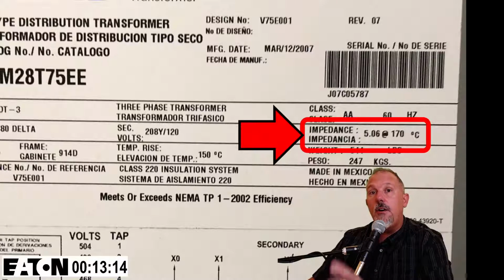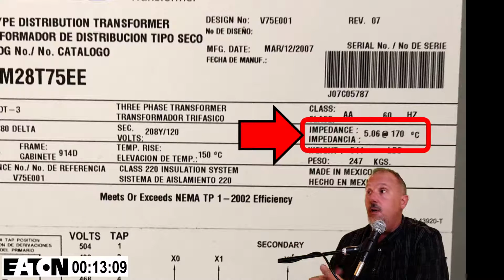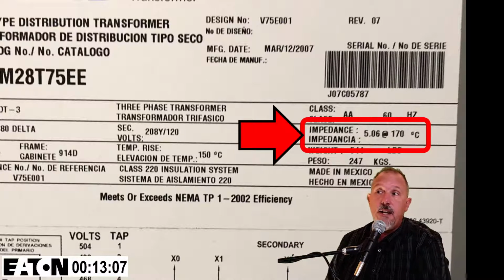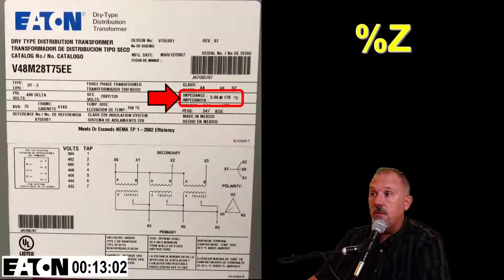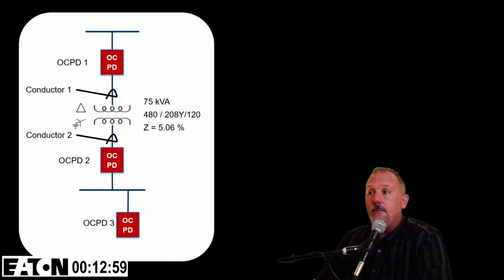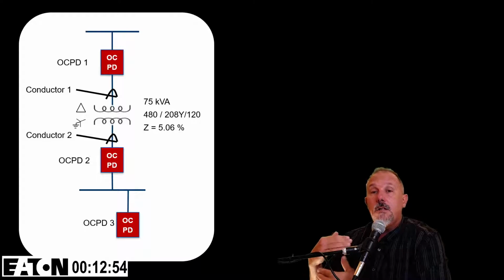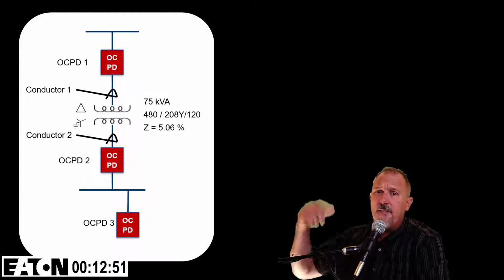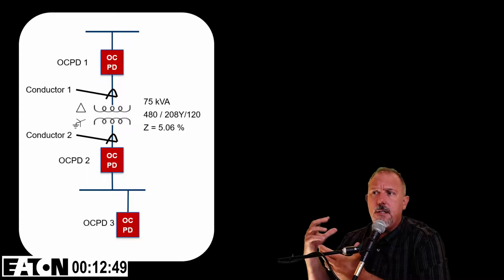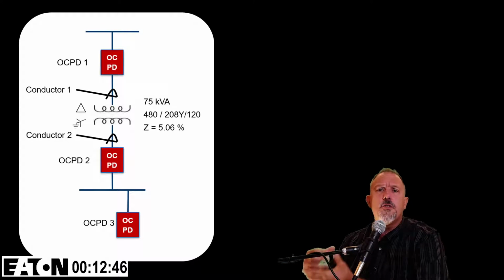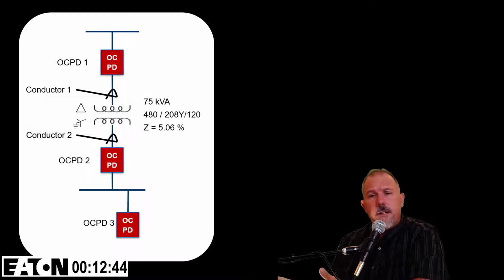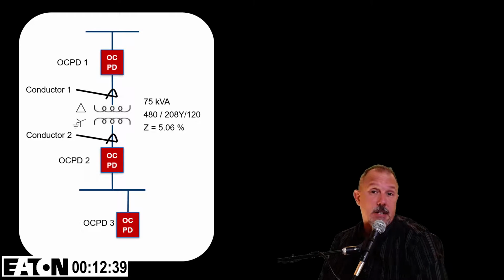The interrupting ratings on the primary devices are going to be driven by the available fault current coming from the upstream source, which could be anything. So it's outside of what I'm going to get into in this session on transformers, because if you really think about that primary overcurrent protective device and its interrupting rating, the available fault current at the terminals of that device, I've got conductor upstream. I may have motor contribution coming from upstream. I might have a really good stiff utility source or whatnot. So it's not what I'm here to talk about.